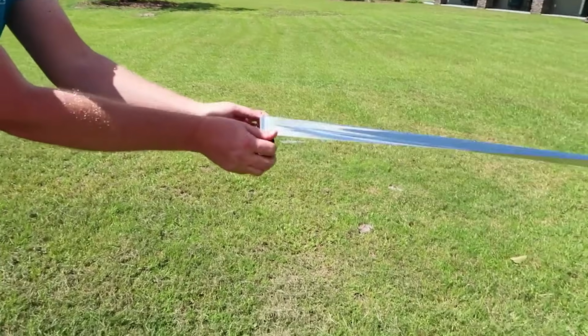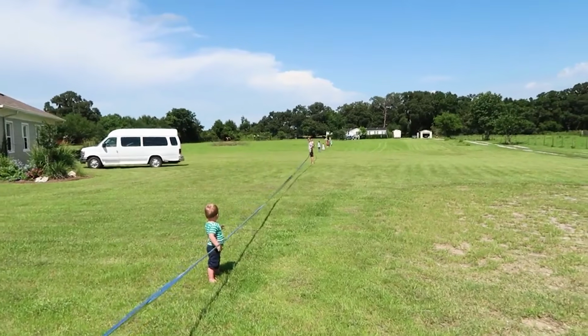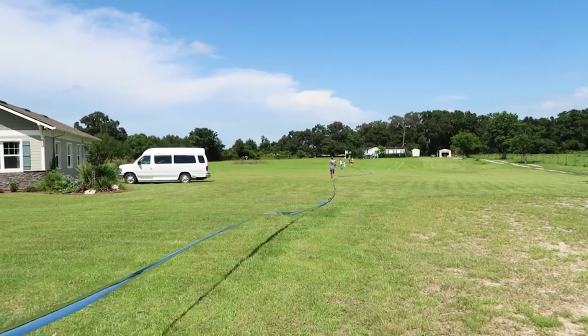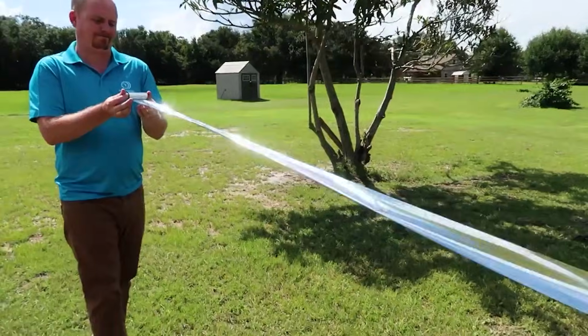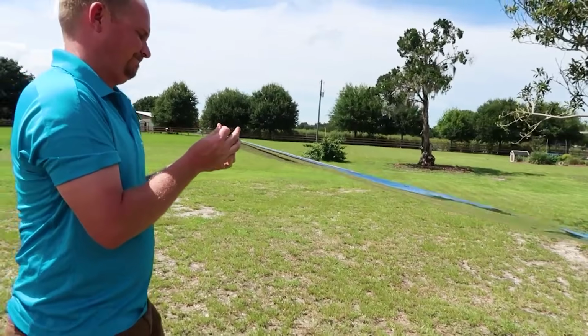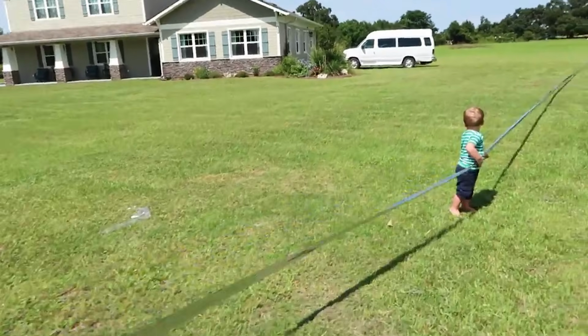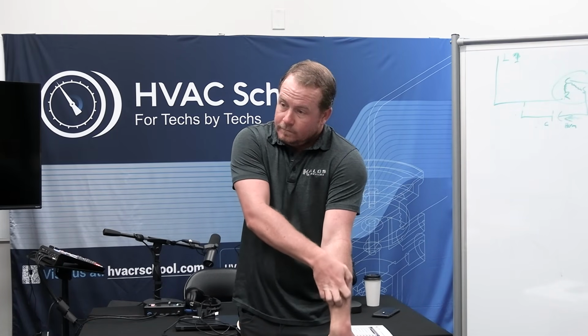So that potential difference is what drives the capacitor, but a capacitor is a super simple thing. It's a run cap, a metal cylinder. Inside is a jelly roll of plastic sheeting with metal coatings on both sides that are connected to the terminals, and a bunch of oil filled in the inside in order to keep it from overheating. That's all. Crazy simple. So if it's dispelling the energy 60 times a second for 60 hertz, what causes the capacitor to store the energy?